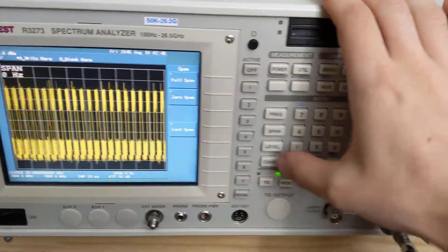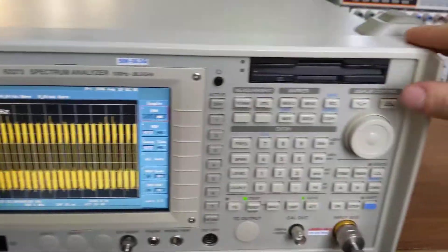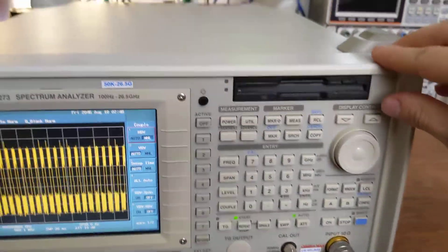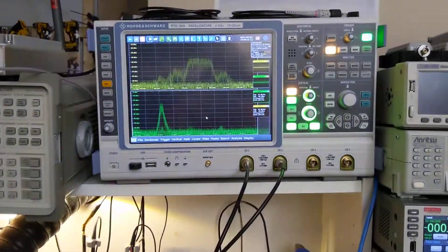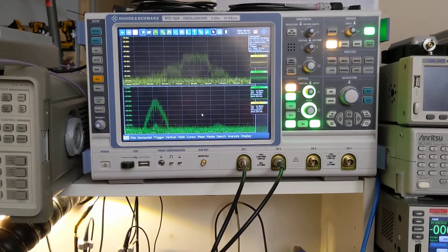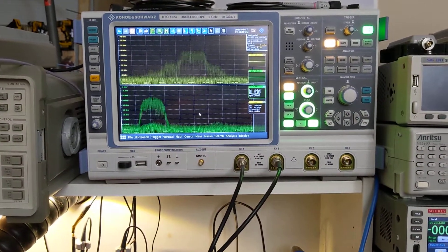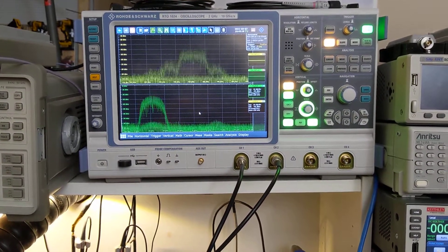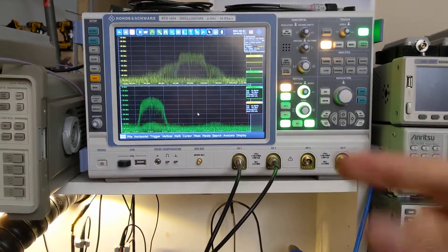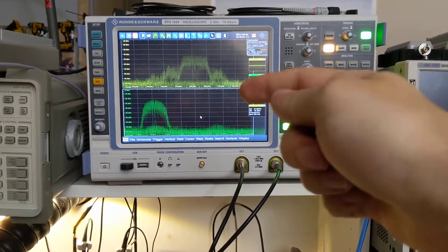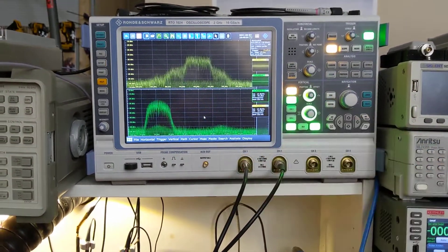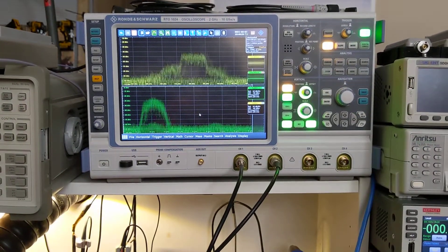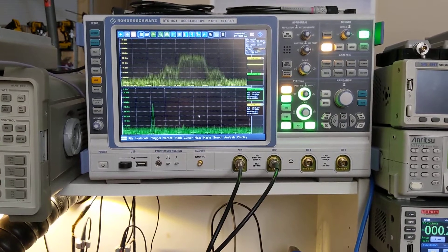So let's play with the RBW filters a little bit here. So RBW manual, I'm going to open those up a little bit and watch the green. So as I open up the RBW filter, you can see more of the WiFi signal makes it through the RBW filter and comes out the 21.4 megahertz IF.